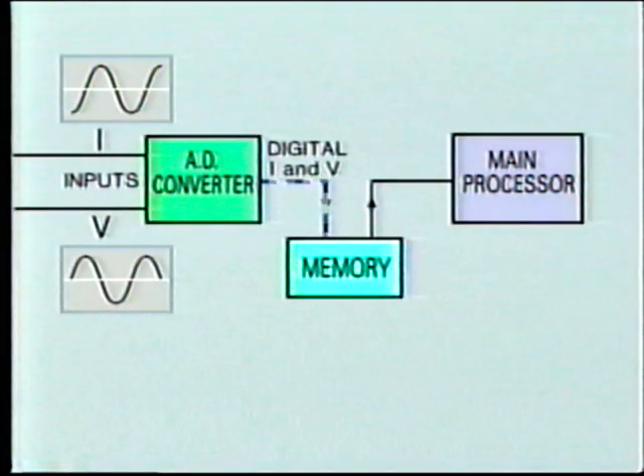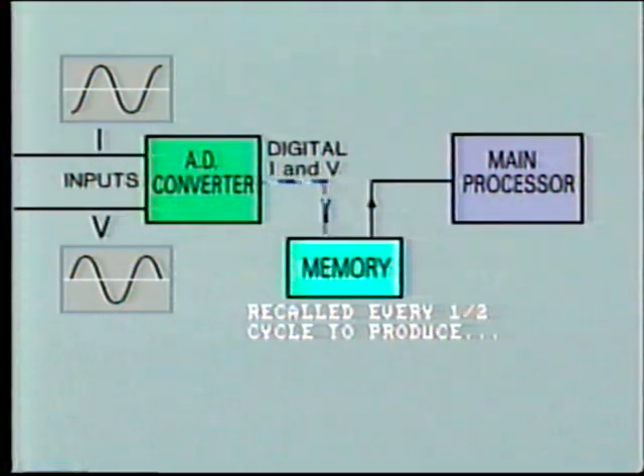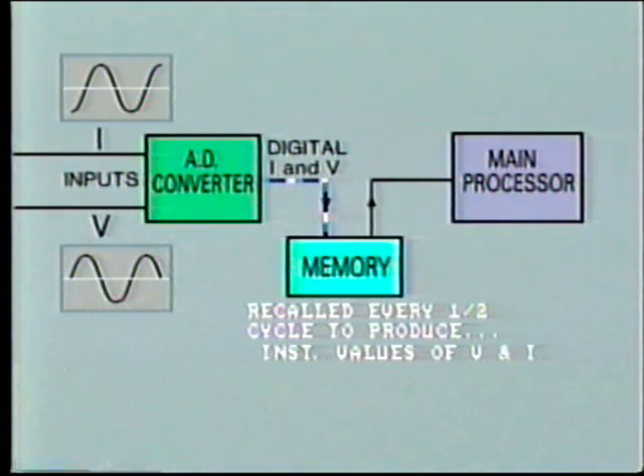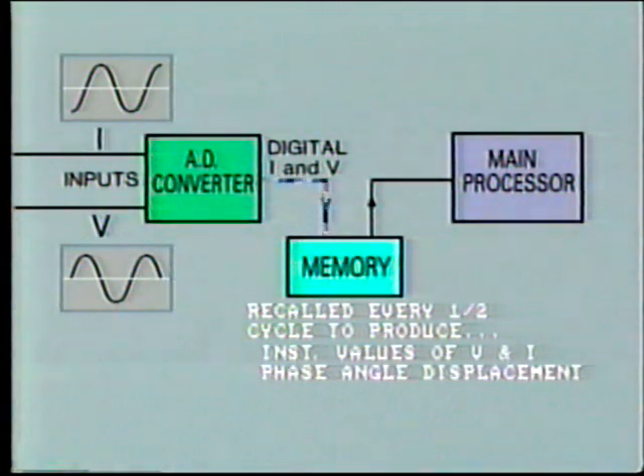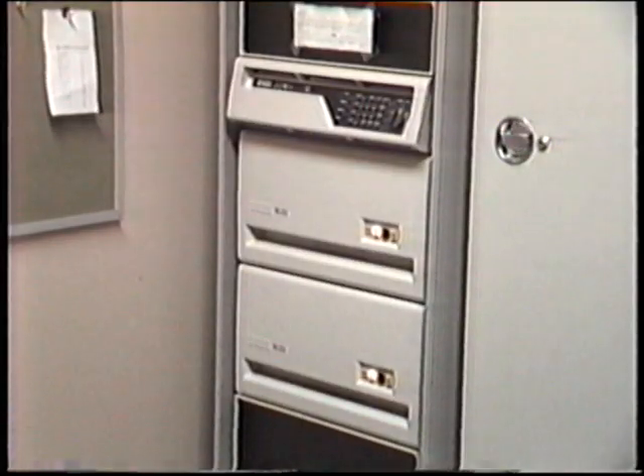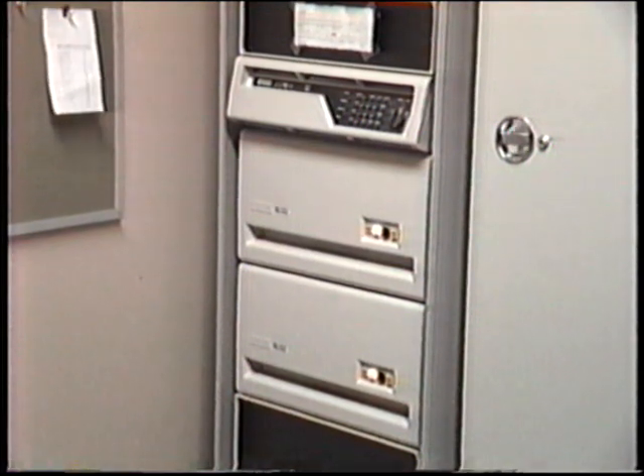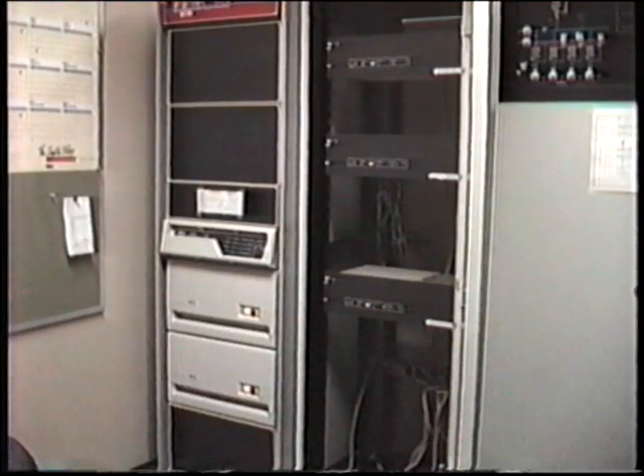The digital signals for input voltage and current are then transferred into a memory to be recalled and processed at specific intervals, say every half cycle or full cycle or 1 second, in order to produce A, instantaneous values of voltage and current, B, phase angle displacement, or C, RMS values of voltage and current. Remember, the significant feature of any computer is that it operates extremely fast and can perform all of these calculations in microseconds. So you can see it is not a difficult task for the processing unit to compare these signals with the reference values at predetermined intervals, perhaps every half a cycle.